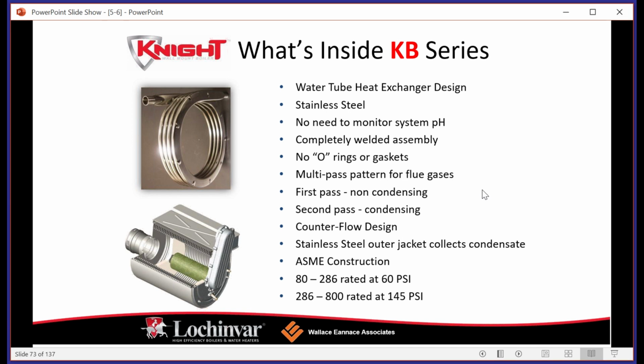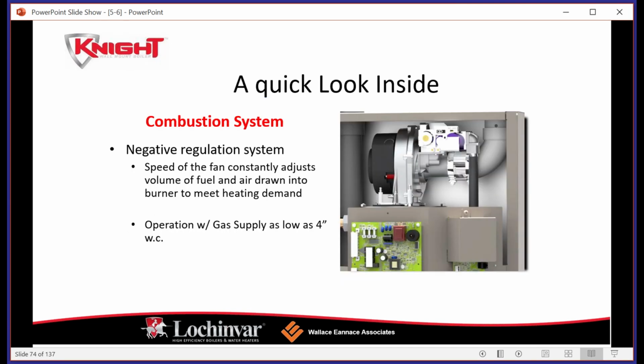This is the inside of a Knight boiler, okay? So we're looking at the combustion system here as well. This is a negative regulation gas valve. And when we discussed that modulation, one of the things we're going to do is speed up and slow down the fans.